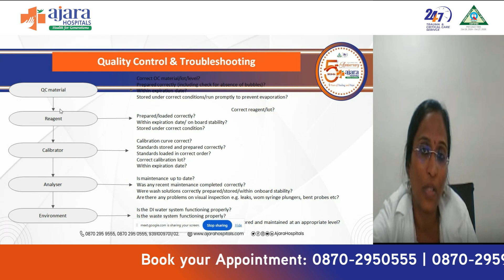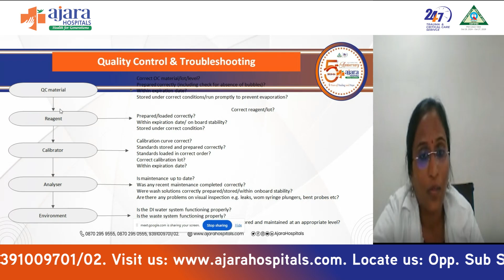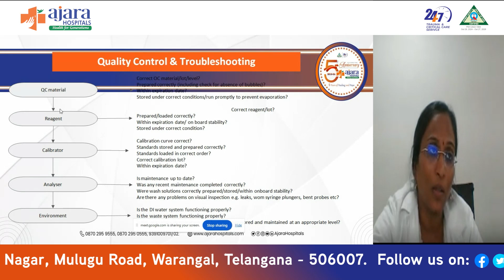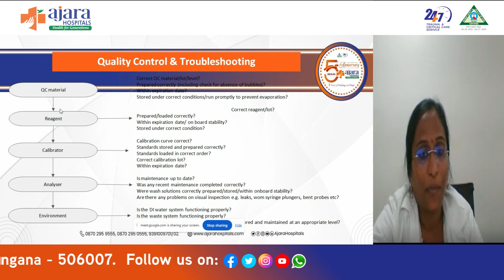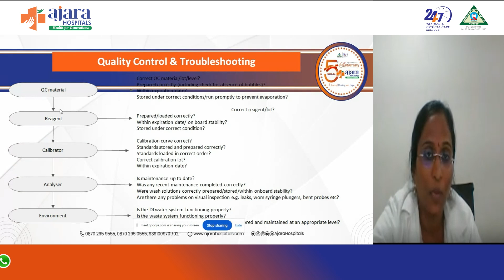Okay, whenever there is a problem, you also have to check the calibration, whether the calibration is correct, whether the curve is correct or not, whether standards are prepared or not. So all that you should be going through. Again, you have to check the analyzer, whether any recent maintenance issue is there, or what is the last time the maintenance person came. All that you have to go back and check. So in a stepwise manner, you can get the root cause for the error, so that you can correct it. And you have to pay attention to the water supply of the lab, whether the distilled water supply is functioning or not. So whenever there is an error in the report, you have to go back and get the root cause, so that you will be able to troubleshoot the problem.